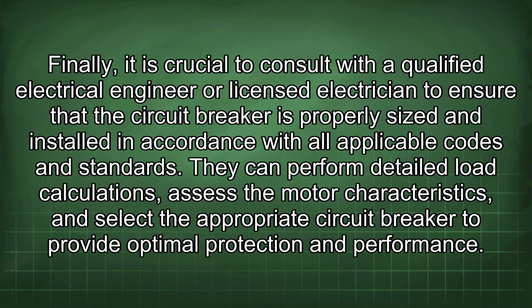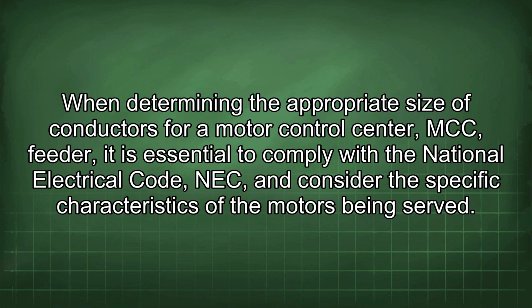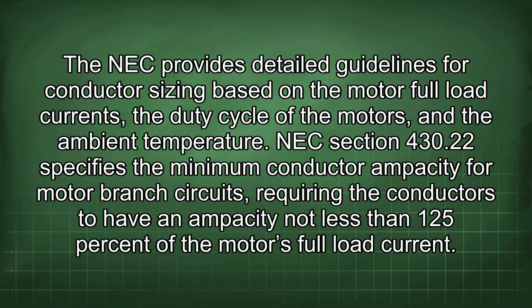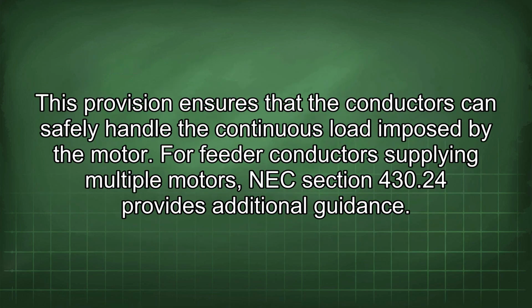and performance. When determining the appropriate size of conductors for a motor control center (MCC) feeder, it is essential to comply with the National Electrical Code (NEC) and consider the specific characteristics of the motors being served. The NEC provides detailed guidelines for conductor sizing based on the motor full load currents, the duty cycle of the motors, and the ambient temperature. NEC Section 430.22 specifies the minimum conductor ampacity for motor branch circuits, requiring the conductors to have an ampacity not less than 125% of the motor's full load current. This provision ensures that the conductors can safely handle the continuous load imposed by the motor.